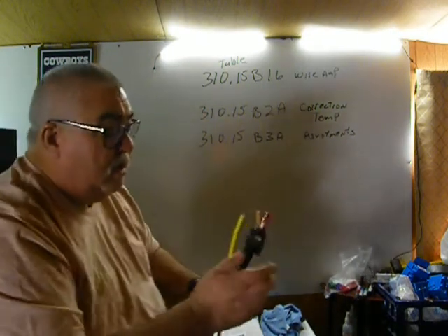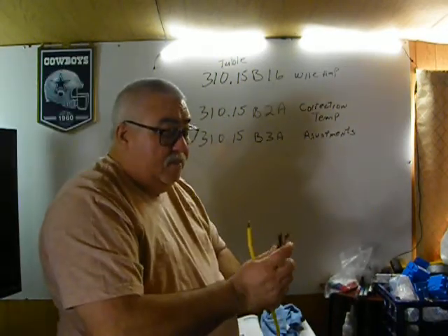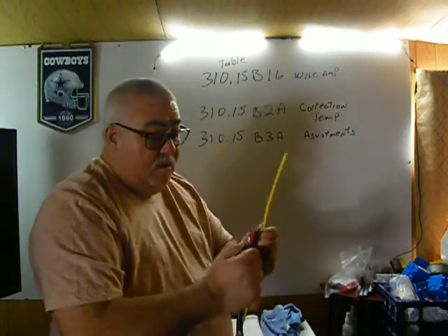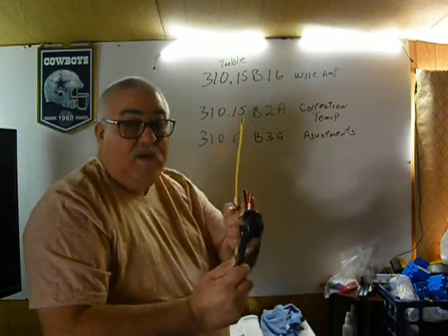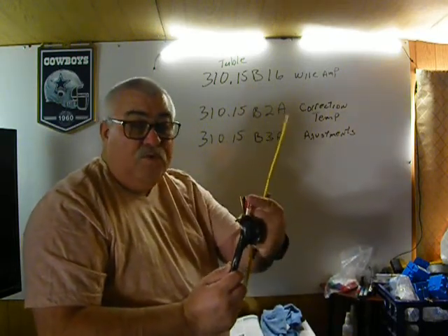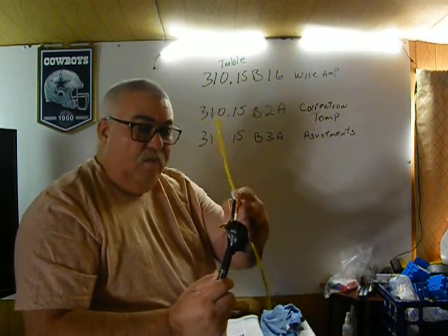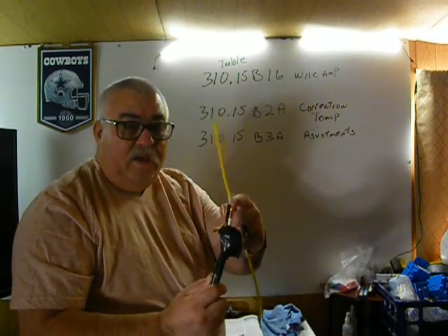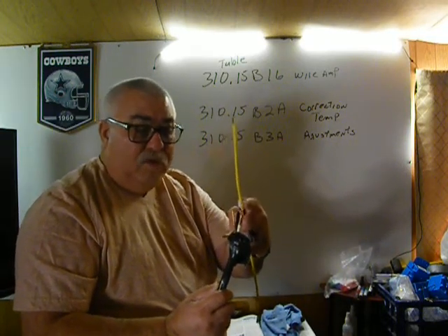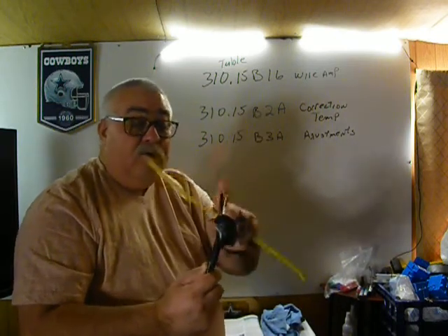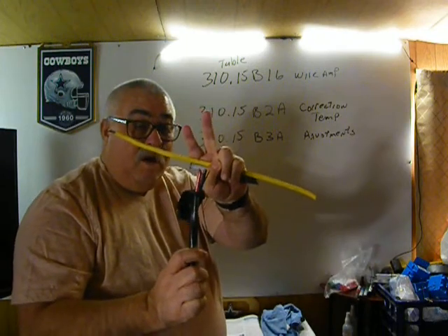Okay, this is a 6-3 with ground. It's got 3 insulated conductors with a ground wire. I only got the possibility of 3 current carrying conductors, but this neutral wouldn't count because whatever is on the black and the red should cancel out. If it's all balanced, it should cancel out. There should be nothing on the neutral. So the neutral is not carrying any current. So that means I only got 2 current carrying conductors.